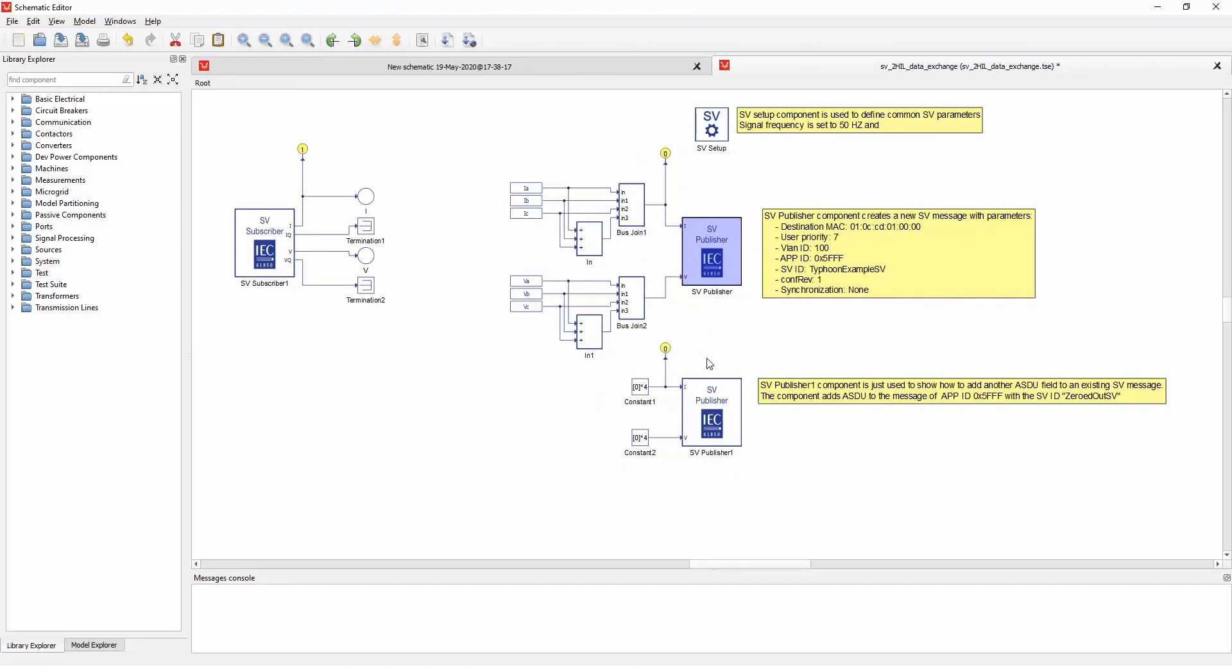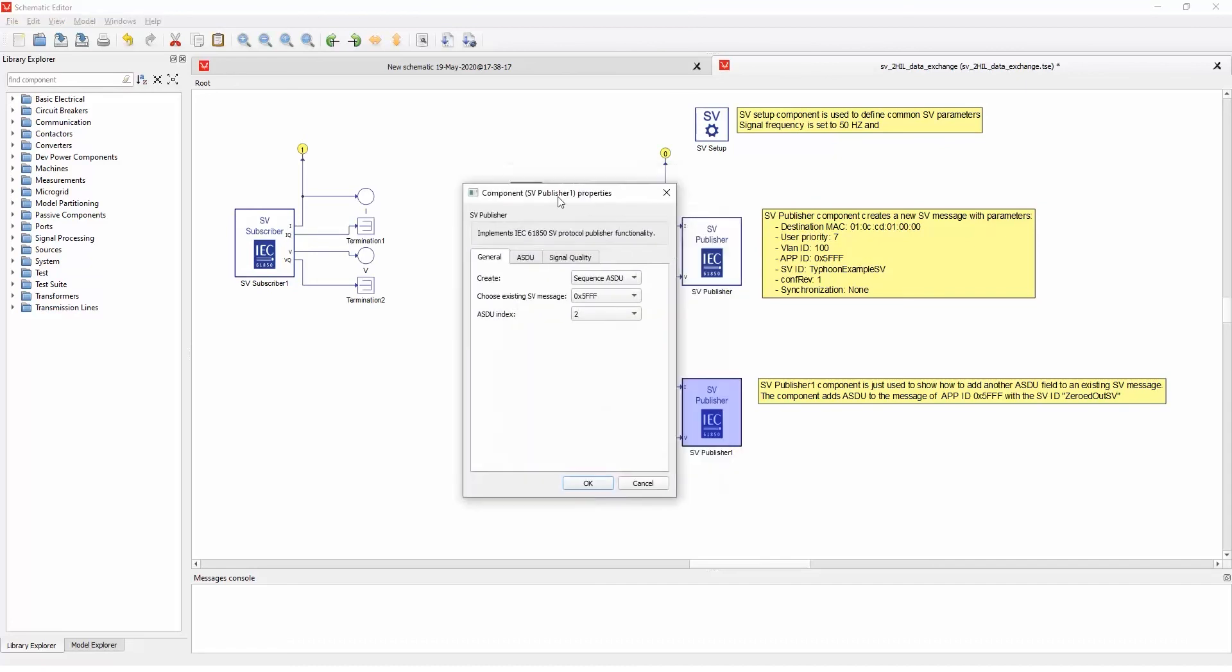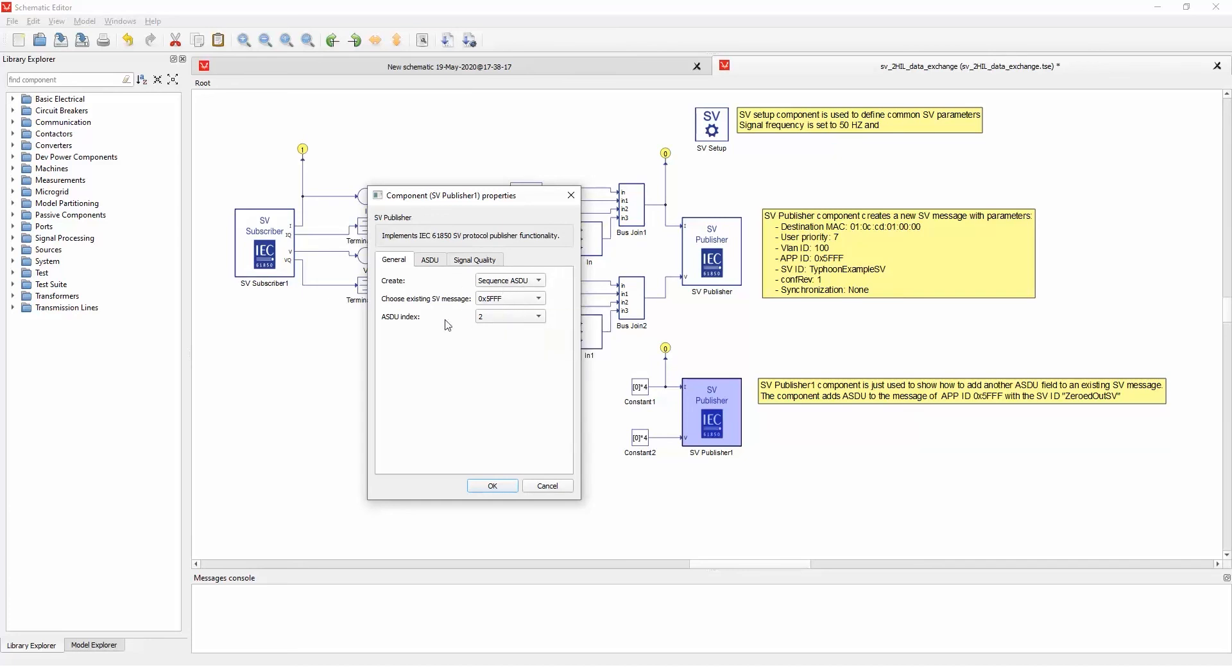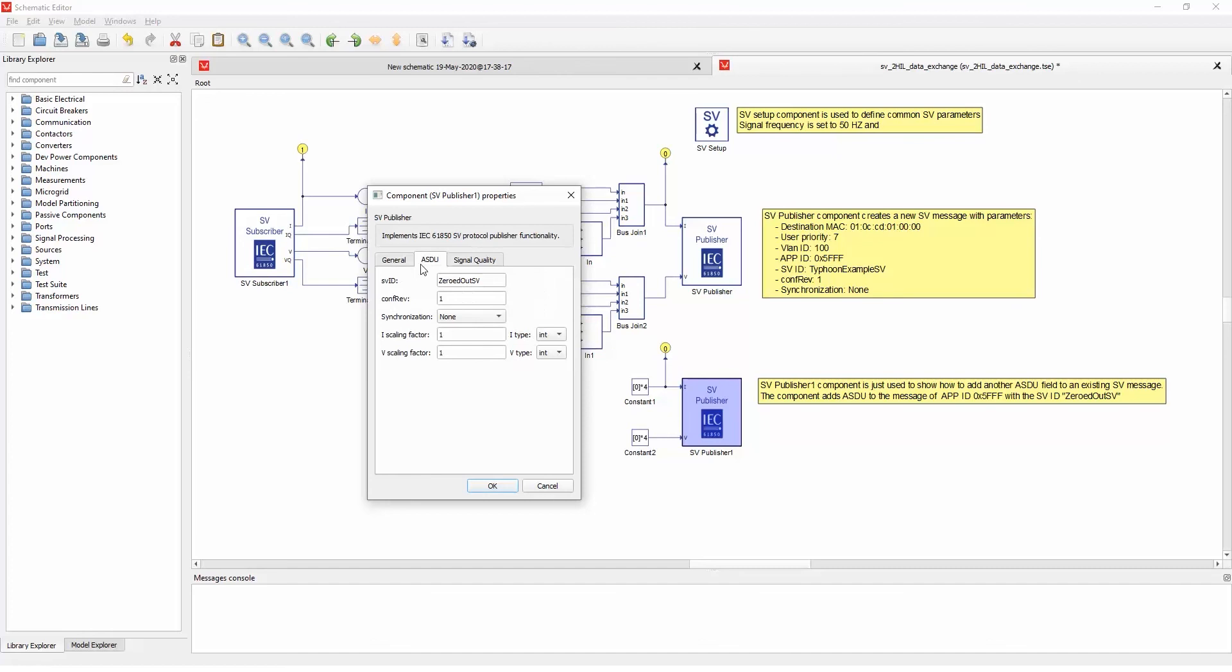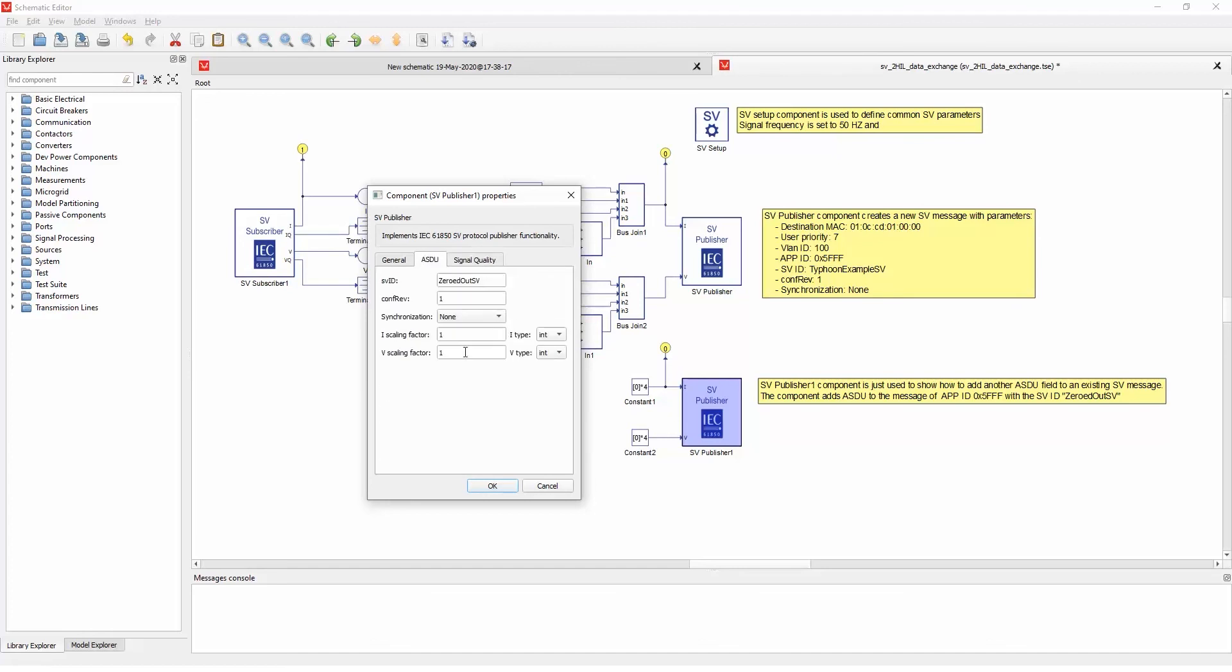And each, if you click on the second one, we can see it's a sequence of application specific data units. So each SV message can have multiple like this sets of current, currents and voltages, and here we just add to the first message data. So we choose the existing SV message, the previous one, and the index of two, and then also define all the other fields.